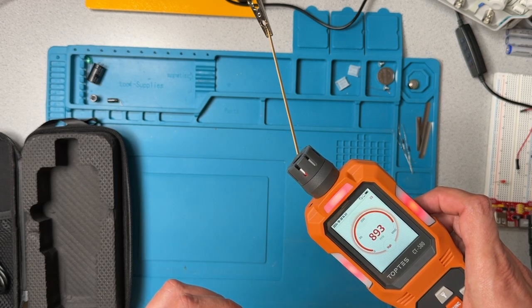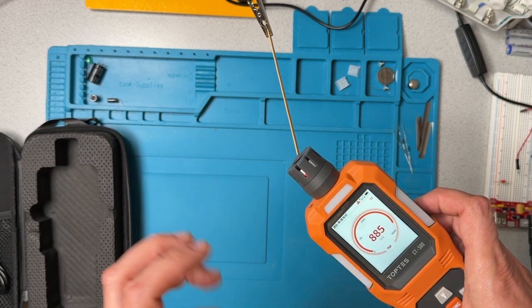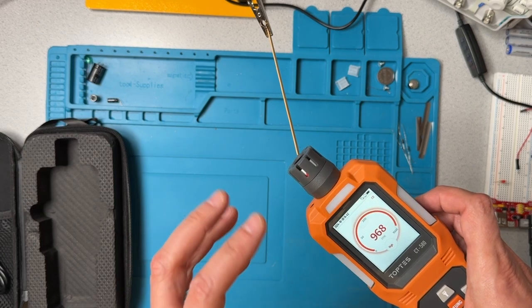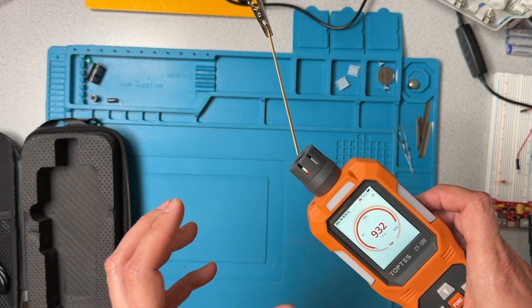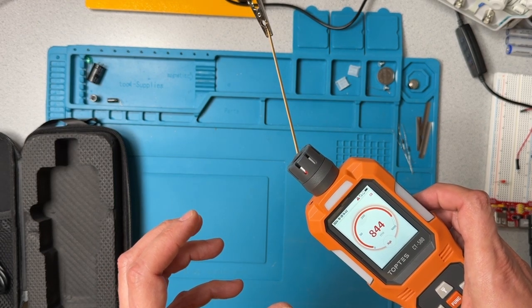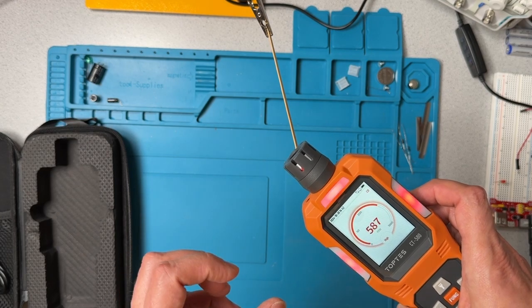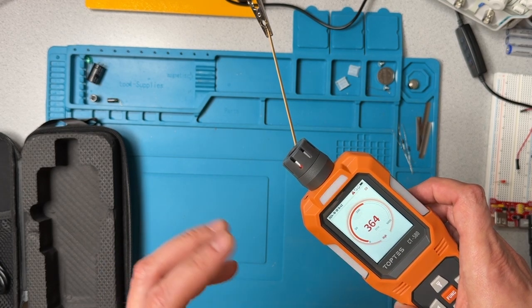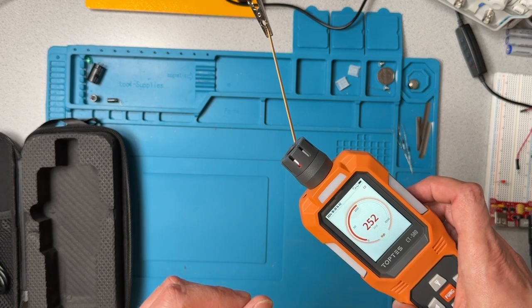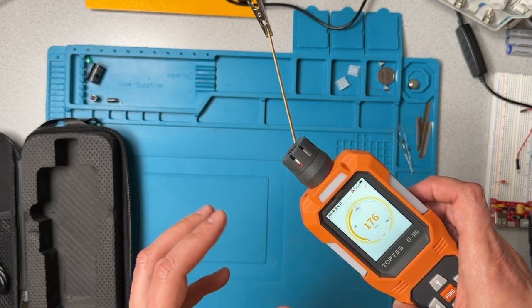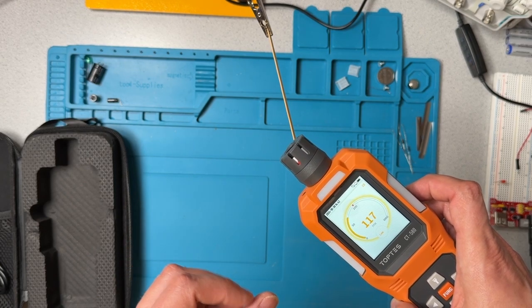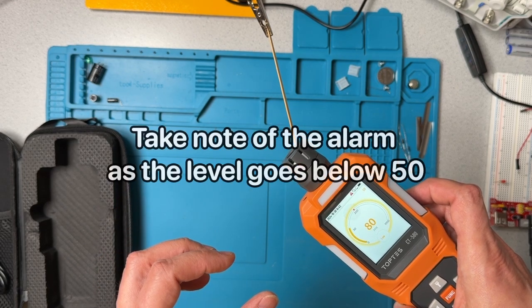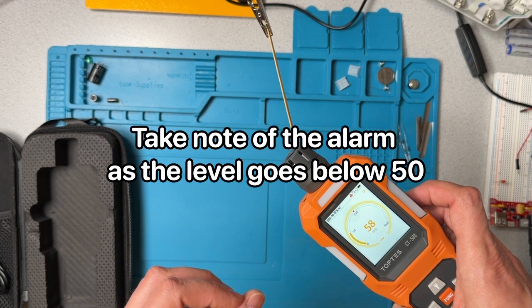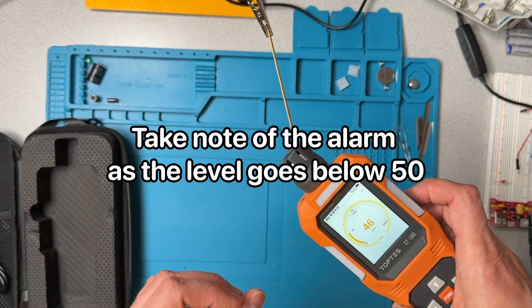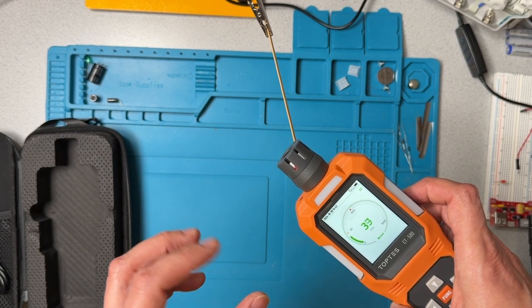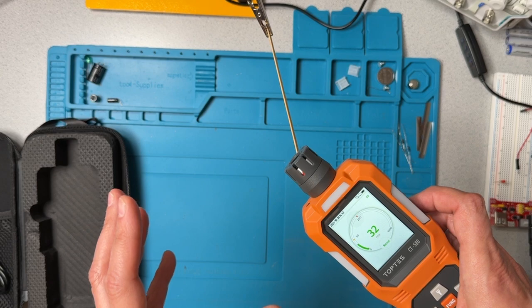You can see that's approaching 1,000 now. The flame has gone out, and so the value is probably going to start dropping now. We can see it's going down, and so we've seen the entire alarm effect. Now as it goes below 200, it'll go from red to yellow. The beeping is slower, and then when it goes below 50, we can see that it's now dropped back to what's considered a normal mode.